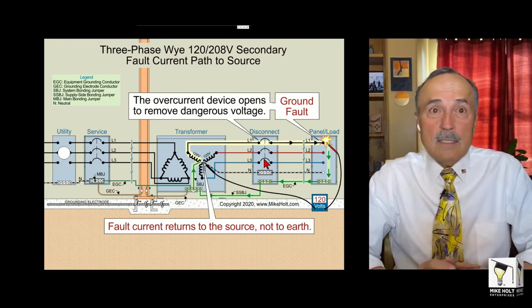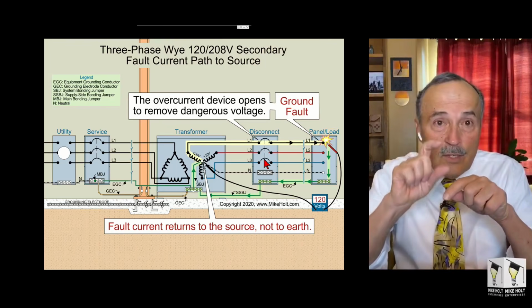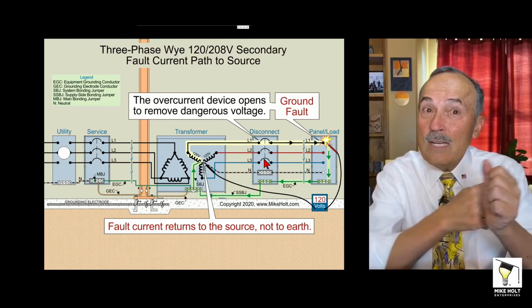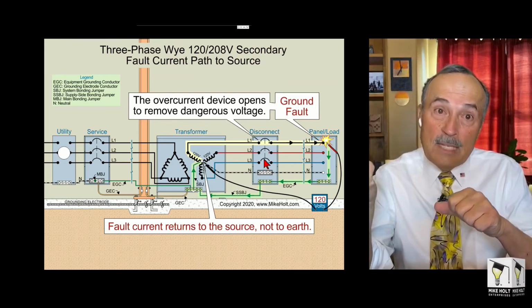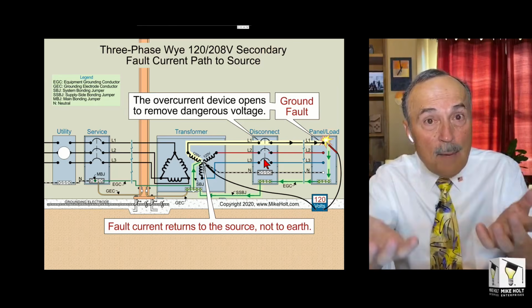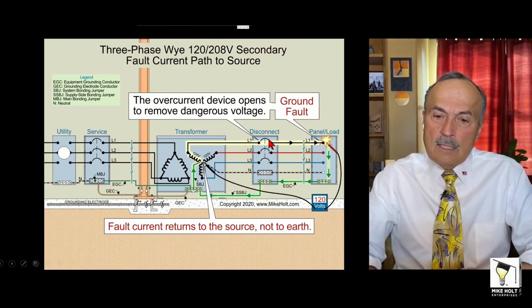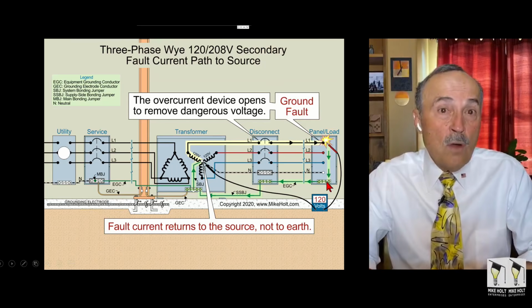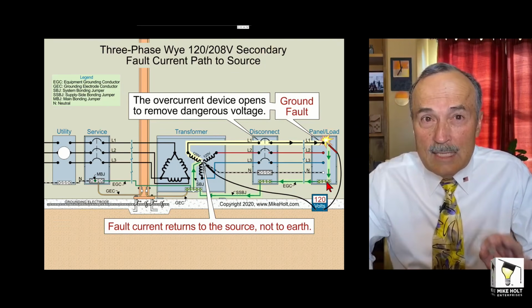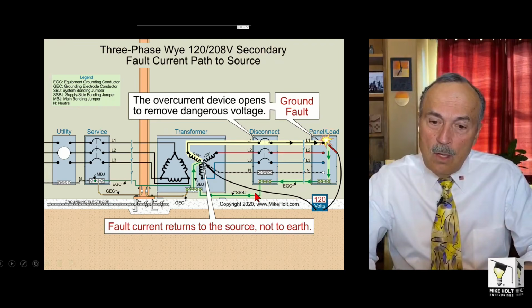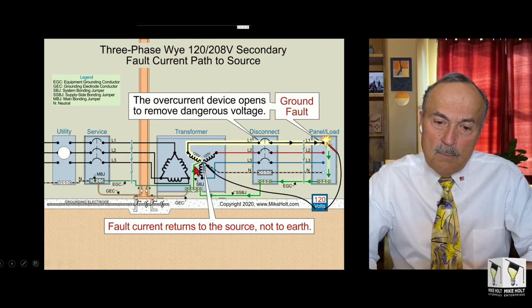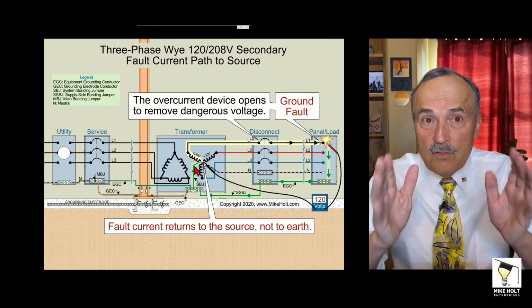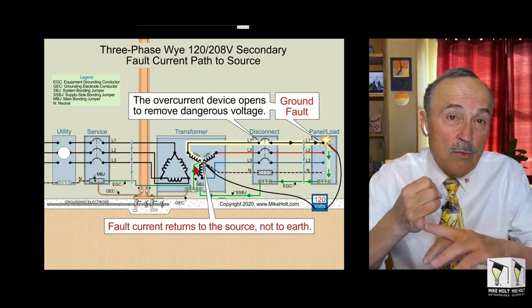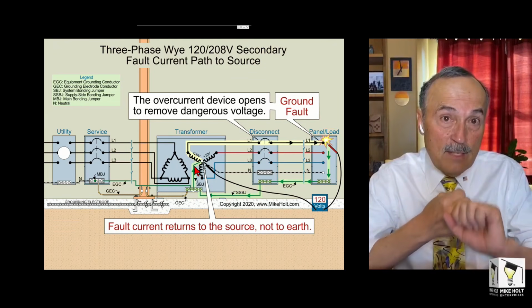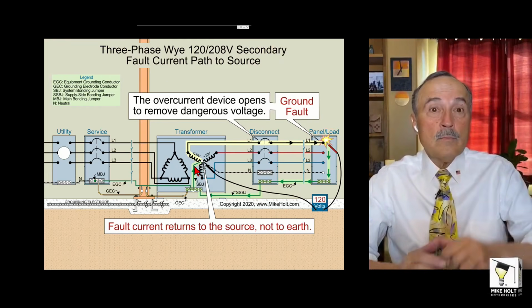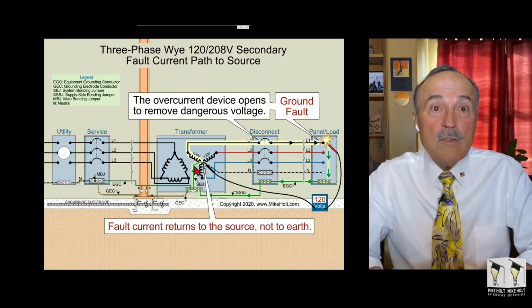Well, in three-phase, Mike, does the fault current get back to the source? Guys, it's only three individual windings that are just connected a certain way, and the electrons leave on the secondary, and the electrons have to get back to the secondary. That's how an electrical circuit operates. It's not that complicated. Electrons leave the secondary, go to the overcurrent device. There's a ground fault. Ground fault current is not going to ground. It's going to go back to the winding itself that it came from. And it goes along the equipment grounding conductor, supply-side bonding jumper, and the system bonding jumper. All those three are part of the effective ground-fault current path as defined in Article 100. And make sure you go to 250.4(A)(5) as well. Clear the breaker, maybe in 0.03 of a second, hundredths of a second.